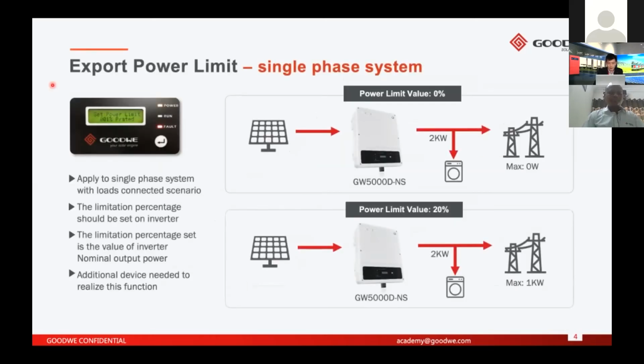And this one is export power limit. In this case, it's a single phase system, and we have some samples here. We can find the PV modules connect to the single phase inverter. The inverter capacity is 5 kilowatt, and the load's consumption is 2 kilowatt. But it's forbidden to output power to the grid, so the maximum is 0 watt. In this case, you can set the power limit value in the display to 0%. So the inverter will only output 2 kilowatt to the loads, and 0 watt to the grid.